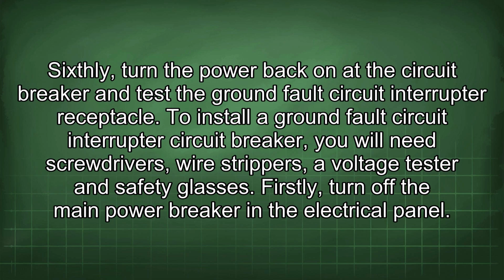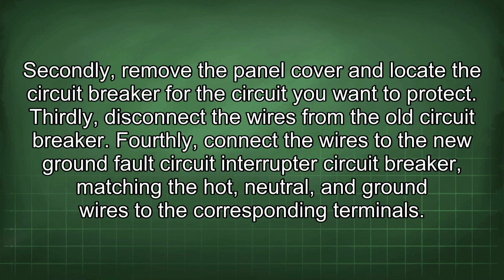To install a ground fault circuit interrupter circuit breaker, you will need screwdrivers, wire strippers, a voltage tester, and safety glasses. Firstly, turn off the main power breaker in the electrical panel. Secondly, remove the panel cover and locate the circuit breaker for the circuit you want to protect. Thirdly, disconnect the wires from the old circuit breaker. Fourthly, connect the wires to the new ground fault circuit interrupter circuit breaker, matching the hot, neutral, and ground wires to the corresponding terminals.